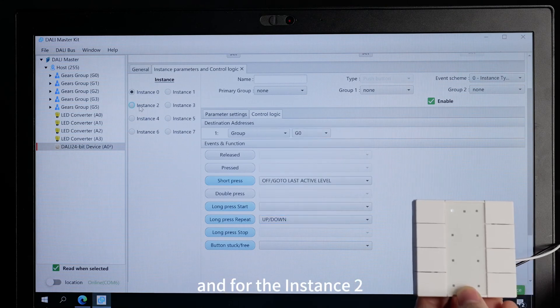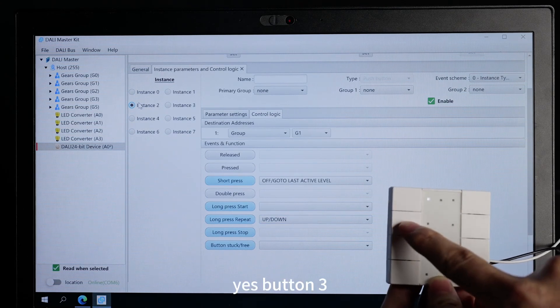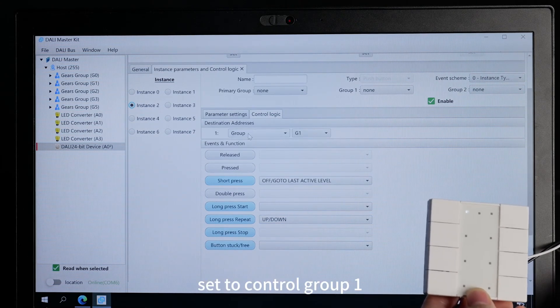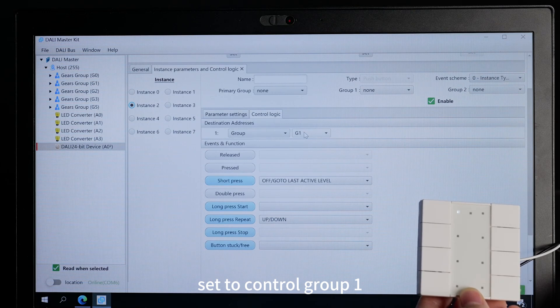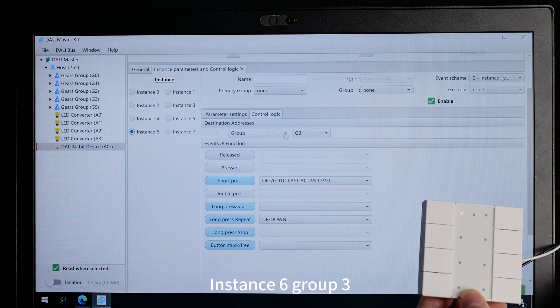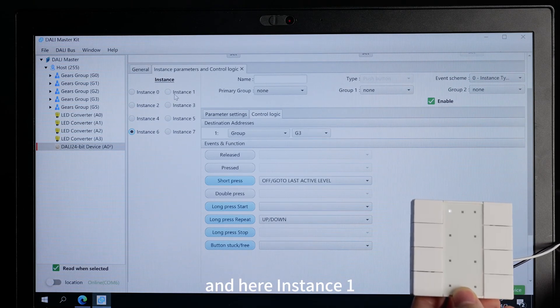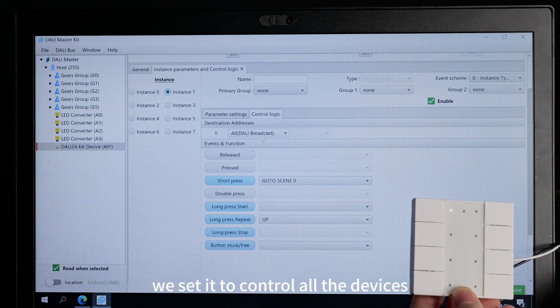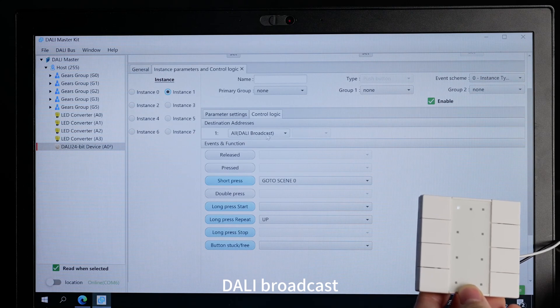For instance 2, button 3 — set to control group 1. And instance 4 for group 2. Incident 6 for group 3. And here, instance 1 — we set it to control all the devices. That is broadcast.